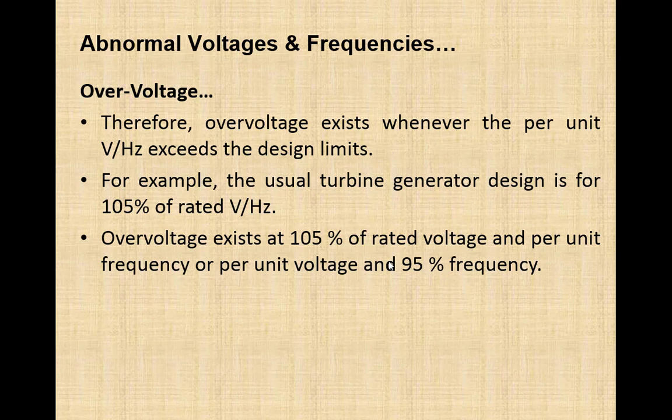Slight overvoltage, you can say within plus 10%, will make operation of motors even better, because the motor will produce more torque and draw less current if the power output is constant. So that's why overvoltage is not problematic for motors.